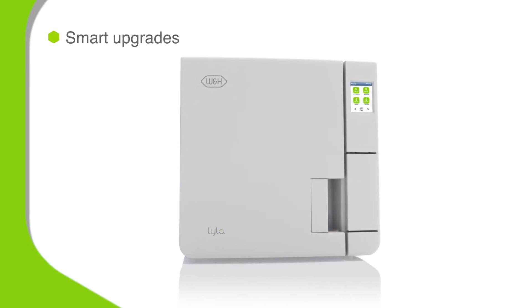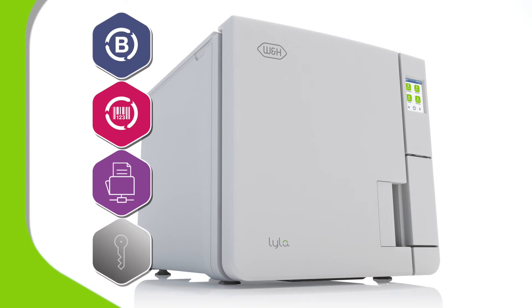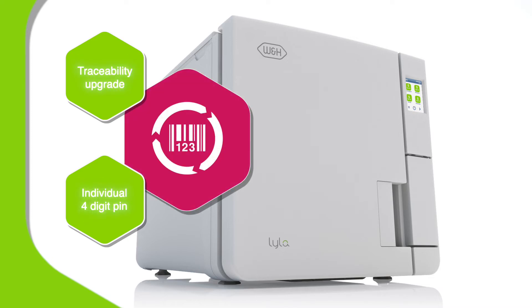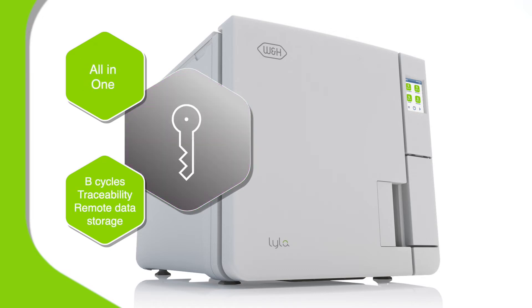Lyla can cleverly adapt to your future needs, whatever they may be. Simply tap in one of four optional activation codes at any time in the life of the machine to upgrade functionality. Activate the B upgrade to enable a choice of fully compliant type B cycles, including a RapidEco B cycle. Activate the traceability upgrade to unlock personalization — each user is given a four-digit pin so any load can be traced back to the individual operator. Or activate the remote data storage upgrade to optimize security and workflow. The combined all-in-one upgrade will activate all enhanced features immediately.